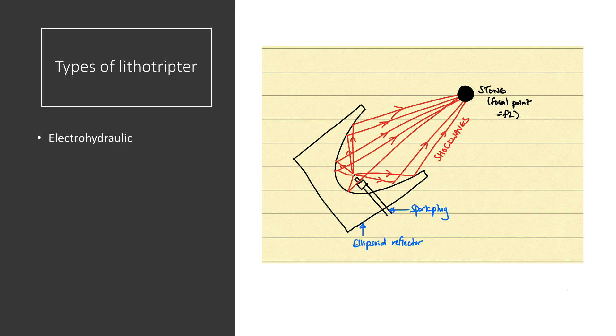As the spark is generated, a shockwave forms around it, and these fan out and are reflected by the ellipsoidal reflector into the second focal point. The key thing is that the spark source has to be positioned at exactly the F1 focal point. Malpositioning it, even by a few millimetres, will substantially reduce the energy at the F2 focal point. Even with very precise alignment, there is slight movement between spark discharges, so the spark-to-spark energy variation is greater than with more modern types of lithotripsy.